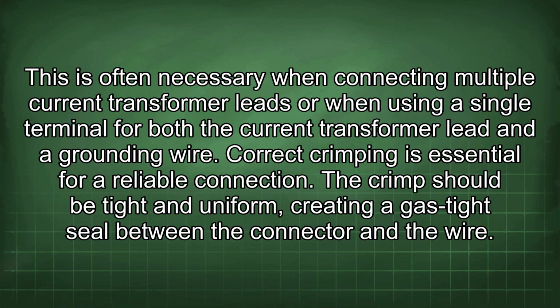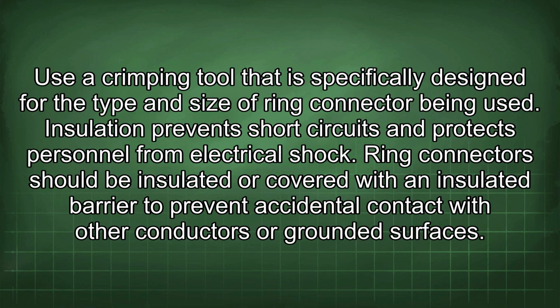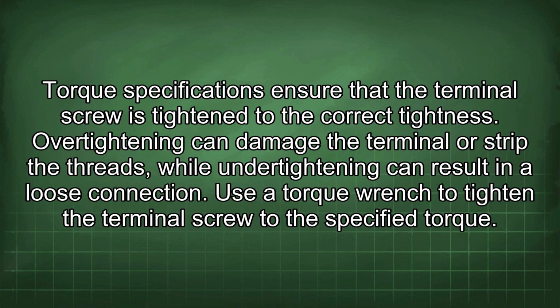Correct crimping is essential for a reliable connection. The crimp should be tight and uniform, creating a gas-tight seal between the connector and the wire. Use a crimping tool that is specifically designed for the type and size of ring connector being used. Insulation prevents short circuits and protects personnel from electrical shock. Ring connectors should be insulated or covered with an insulated barrier to prevent accidental contact with other conductors or grounded surfaces. Torque specifications ensure that the terminal screw is tightened to the correct tightness. Over-tightening can damage the terminal or strip the threads, while under-tightening can result in a loose connection.